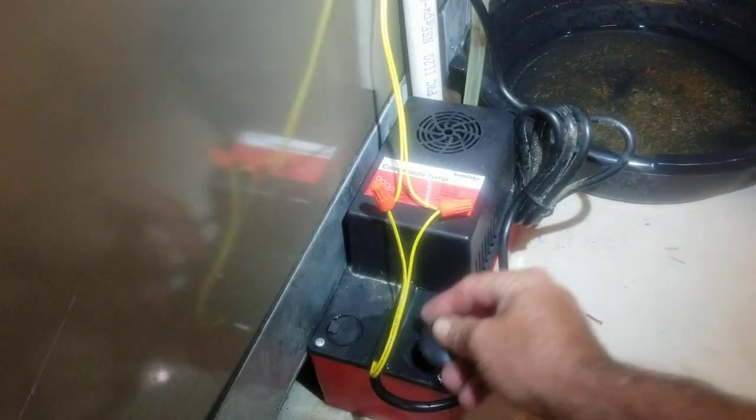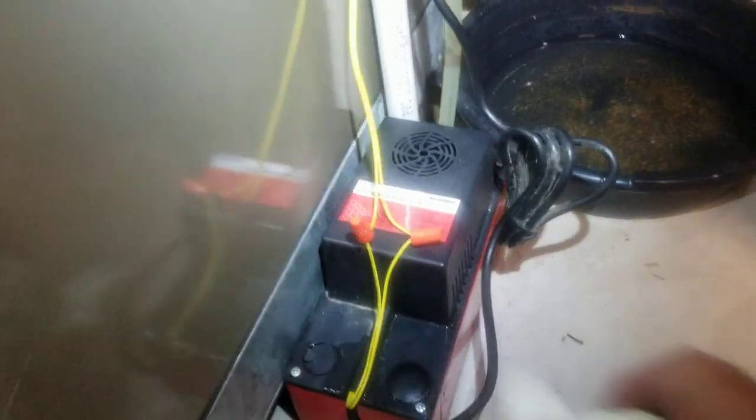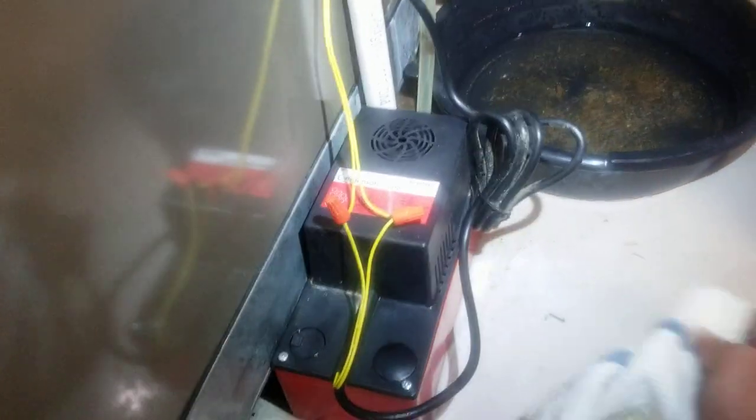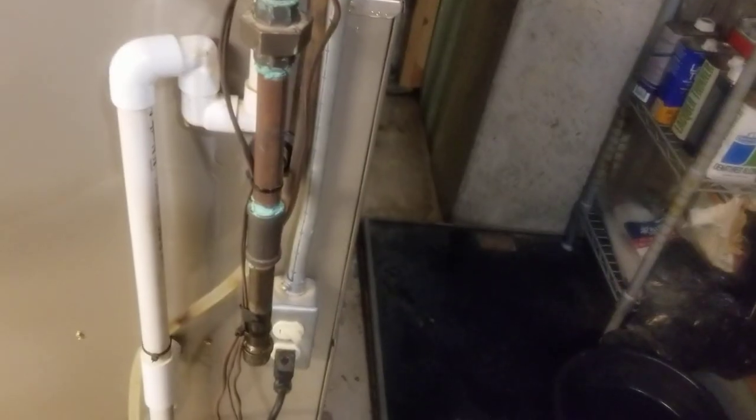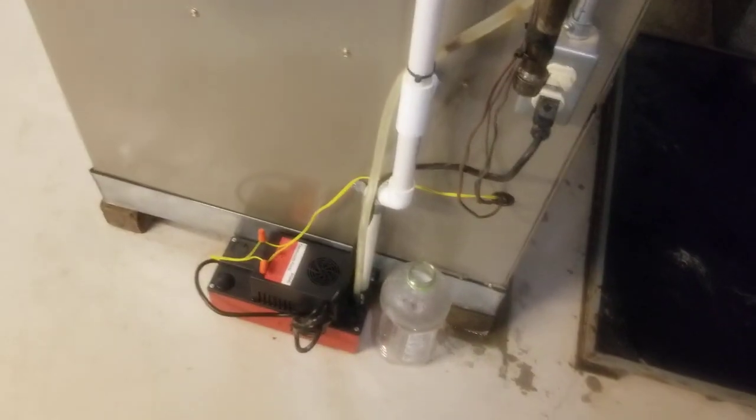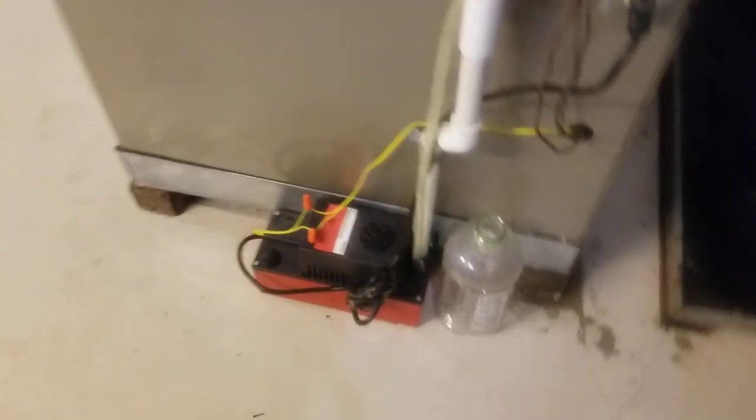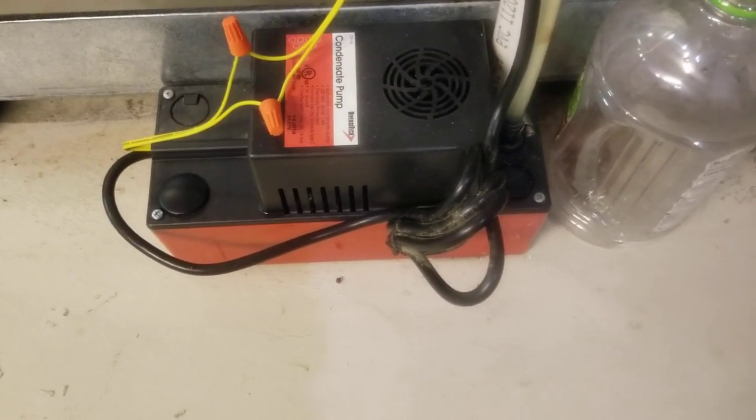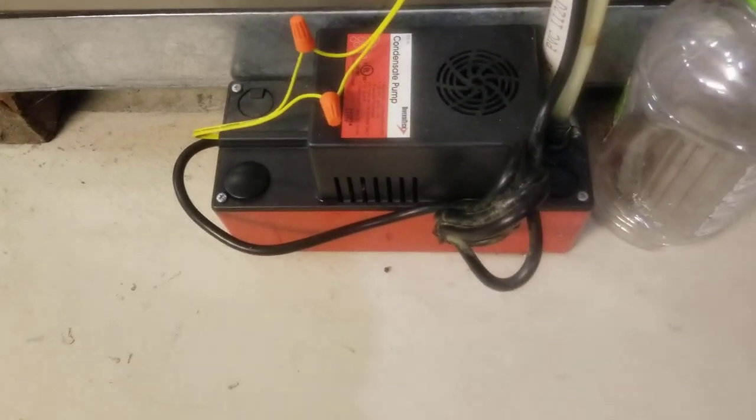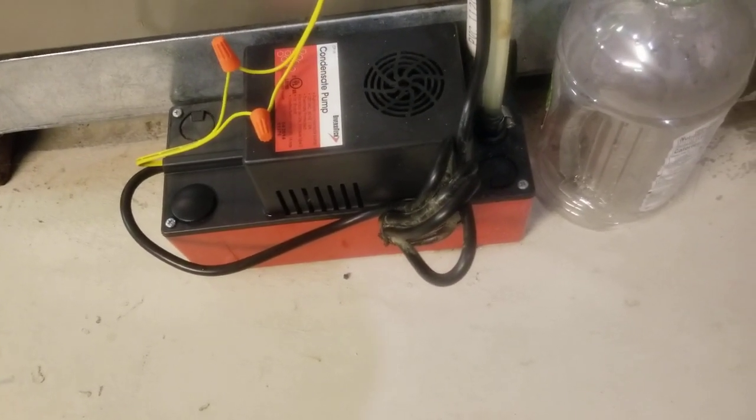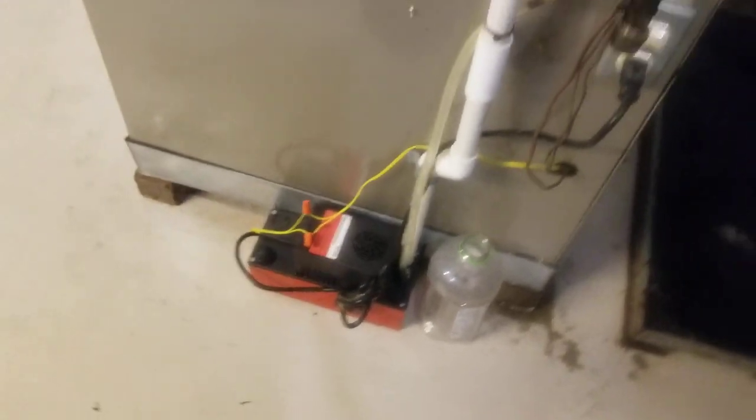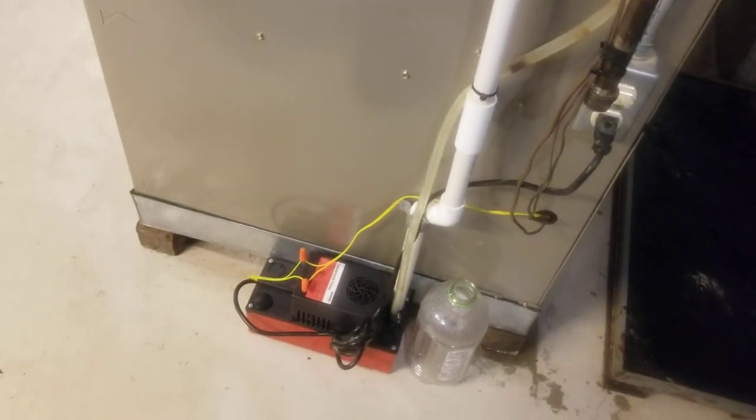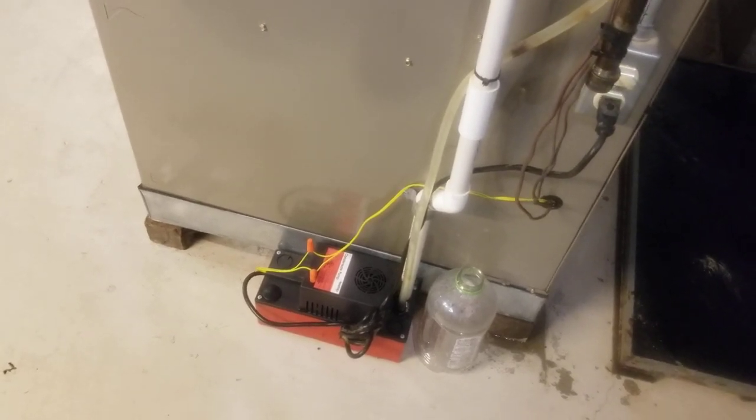Everything is working, we are done. So if you think you got a bad pump, check the check valve. Just make sure you cover all your bases before you condemn a condensate pump, because it might just be dirty. I had a condensate pump sitting there ready to go, and I'm like, let me check. Those are some of the things you got to do to make sure you get the proper diagnosis.